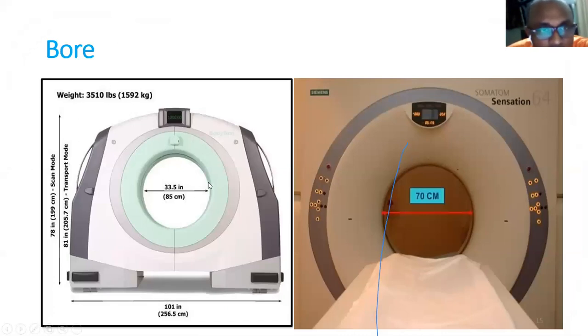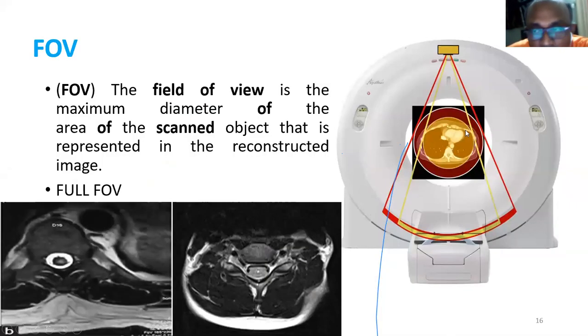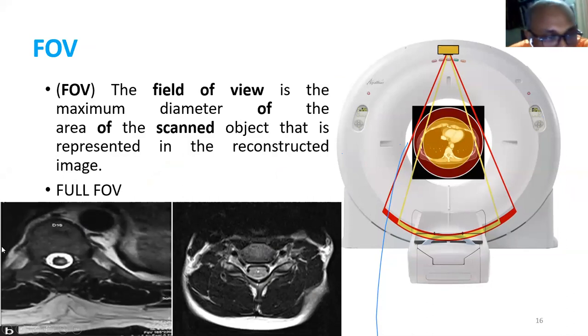Bore is the total opening aperture of the CT or MR scanner. FOV, or field of view, is the maximum diameter of the area of the scanned object represented in the reconstructed image. A small FOV gives good resolution but covers a limited area. A full FOV captures the total image. For CT-MR fusion in stereotaxy practice, we need to take the full FOV.